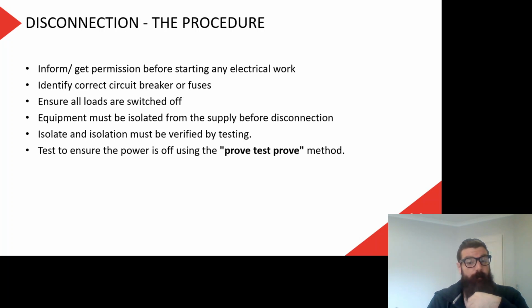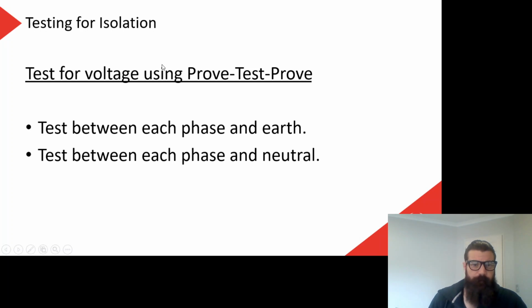And then we isolate, and the isolation must be verified by testing. So we switch it off, then we go and test the thing that we're going to work on, as we just said, prove, test, prove, to make sure that we have definitely switched that off. Testing for isolation, if we test for voltage using prove, test, prove, as I said before, we test between each phase and earth and test between each phase and neutral. If it's one phase, then it's just phase to earth, phase to neutral. If there's multiple phases, then we test every single one of those phases to both neutral and earth. That is to make sure that everything is dead.